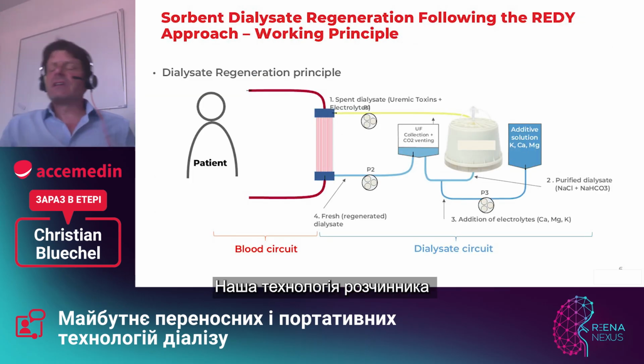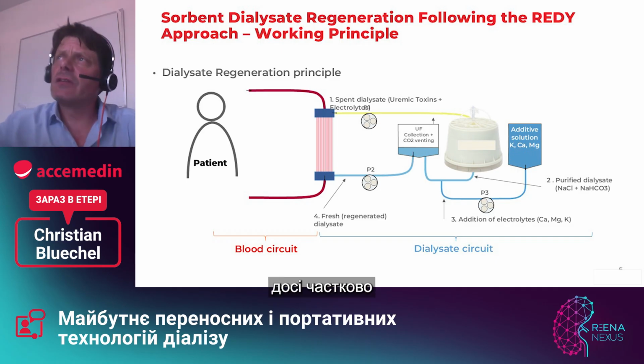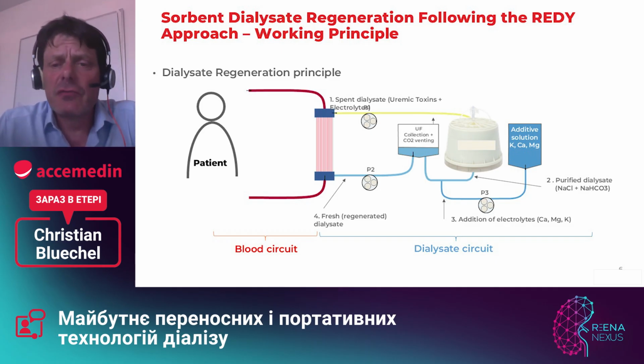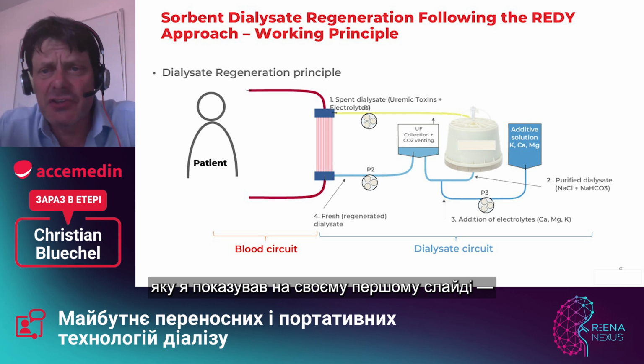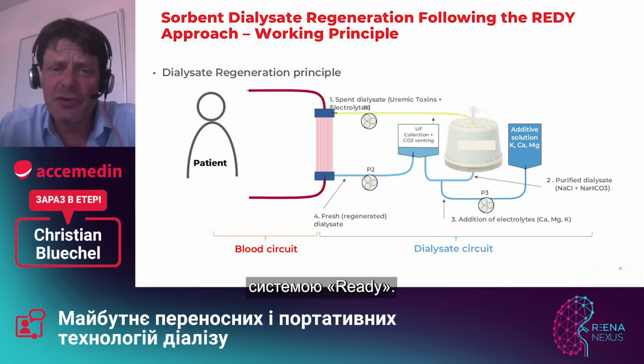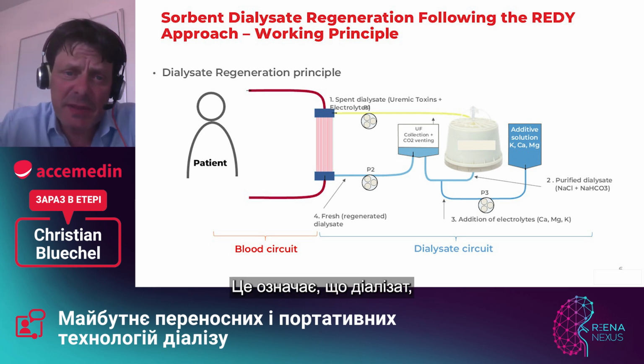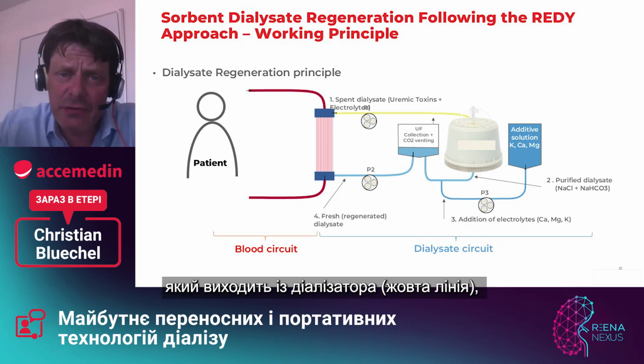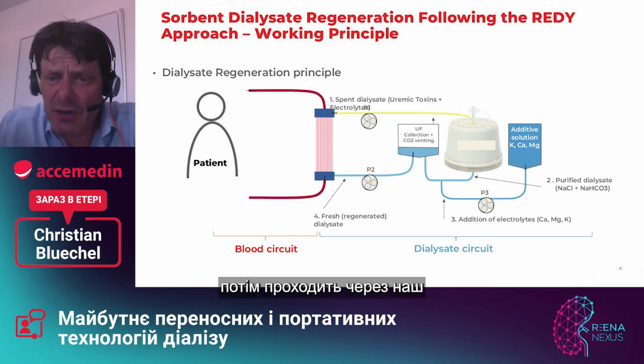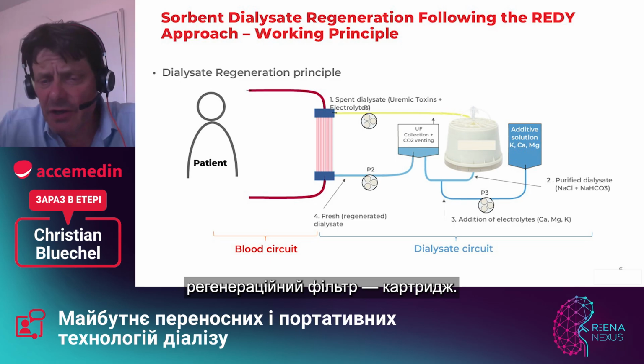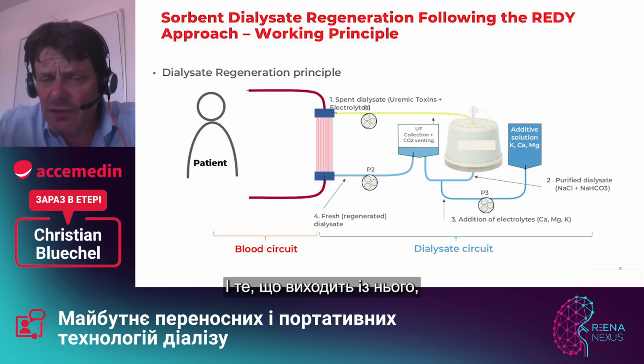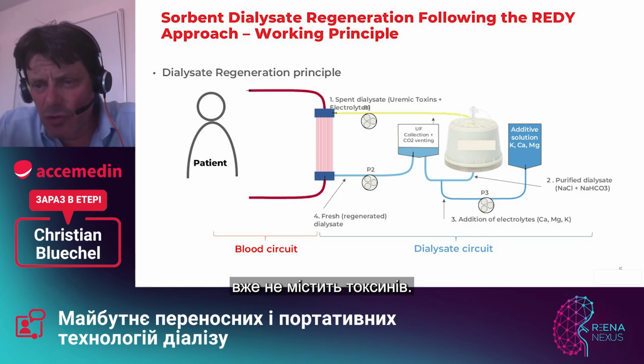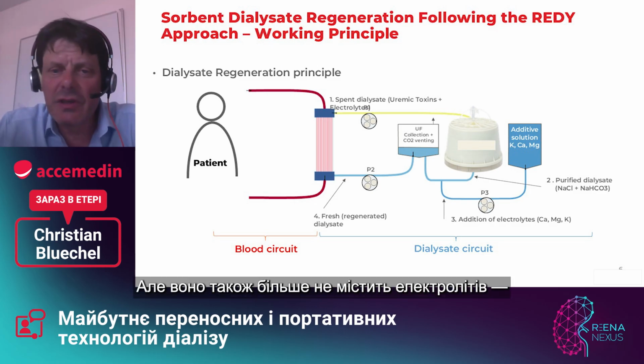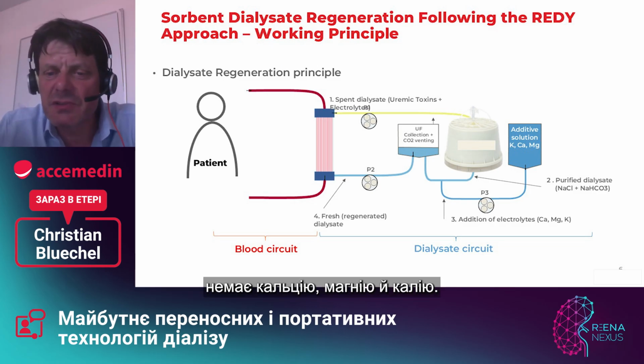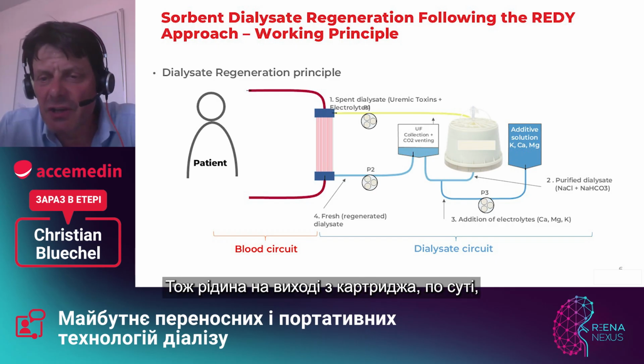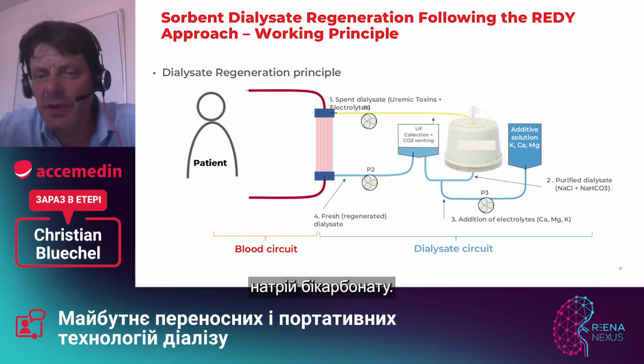Our sorbent is using a technology which is still remotely related to that of that first machine that I showed on my first slide, the REDY approach. And what this means is that we have spent dialysate coming from the dialyzer, that is the yellow line, which then passes through our regeneration filter, our cartridge. And then what comes out of here contains no more toxins, but also no more electrolytes. There's no calcium, magnesium, and potassium. So the outflow of the cartridge is essentially a solution of sodium chloride and sodium bicarbonate.